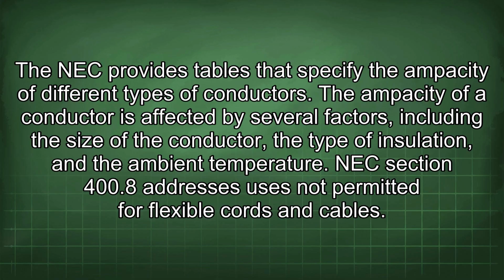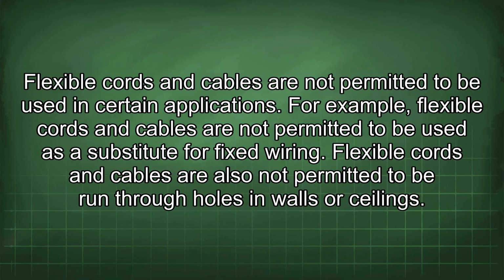and the ambient temperature. NEC Section 400.8 addresses uses not permitted for flexible cords and cables. Flexible cords and cables are not permitted to be used in certain applications. For example, flexible cords and cables are not permitted to be used as a substitute for fixed wiring. Flexible cords and cables are also not permitted to be run through holes in walls or ceilings.